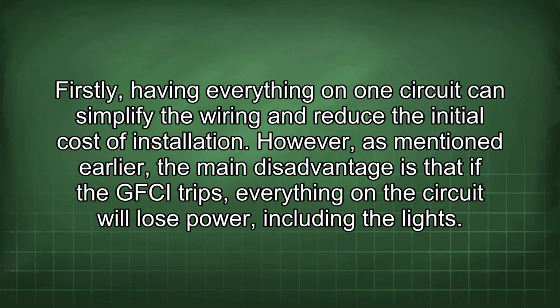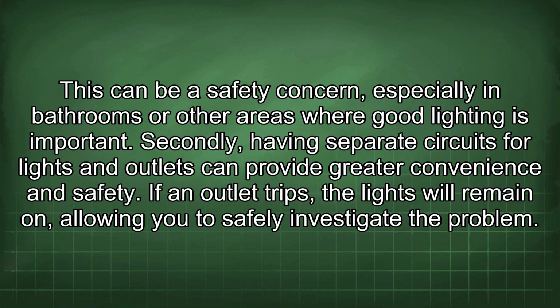Firstly, having everything on one circuit can simplify the wiring and reduce the initial cost of installation. However, as mentioned earlier, the main disadvantage is that if the GFCI trips, everything on the circuit will lose power, including the lights. This can be a safety concern, especially in bathrooms or other areas where good lighting is important.